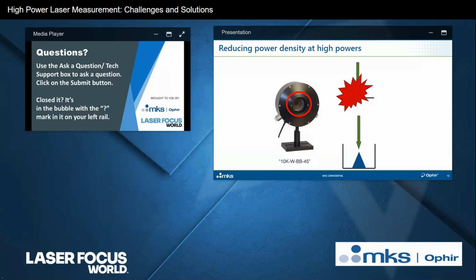Now the beam comes in, and instead of hitting the absorber, it first hits this reflective cone and gets deflected radially outward, spread around a full 360 degrees with a divergence angle. So the power density that's actually reaching the absorber, the cylindrical vertical wall around that cone, has been significantly reduced from what it was when the beam was originally coming in, and that allows the sensor to handle higher power densities than it otherwise would have.